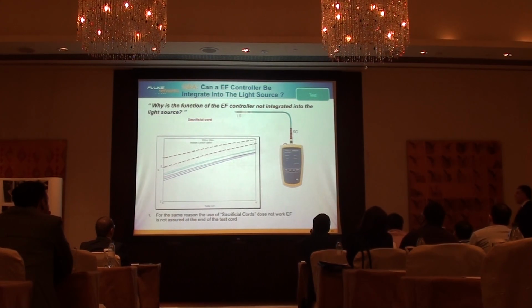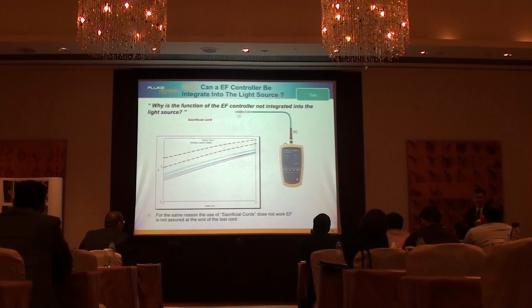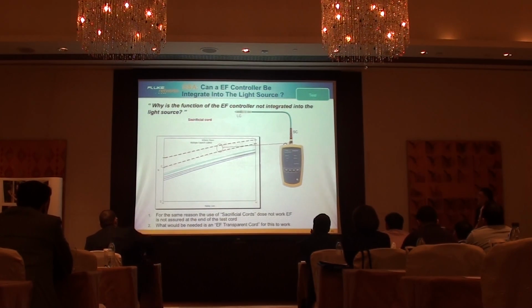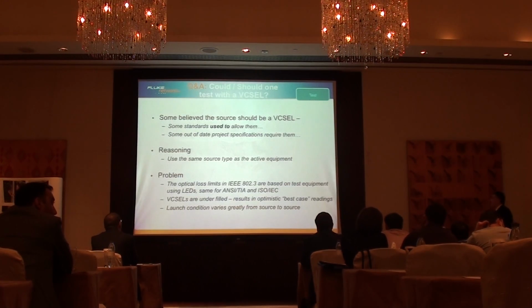And also the measurements that they have done, even though this is your template, if you use a regular cord, even though the light that comes out of the tester is EF compliant, it will fall below the template. So you have to have a specific cord for this. So it will not work. Even though your device is EF compliant, that cord is very critical.